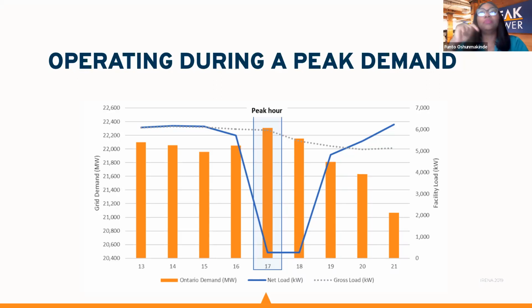So at this point, the battery was being discharged to reduce the consumption of the site. So at hour 17, where the grid demand was the highest, the battery was used to discharge the most to reduce the consumption of the building from the grid at that hour, thereby reducing the demand of the building during the top peak demand hour, thereby generating savings for the building, right? So this is just a brief description of how the battery can be operated during a coincident peak event and generating savings for the site. Next slide, please.